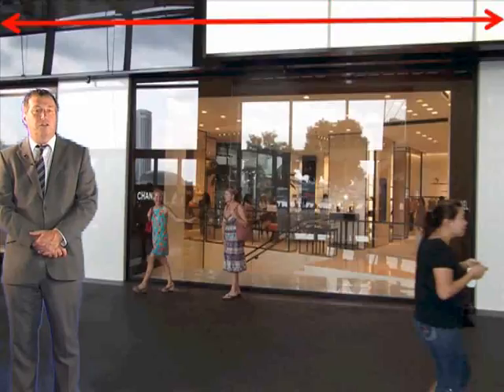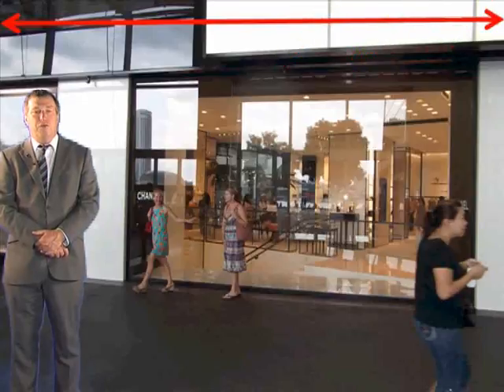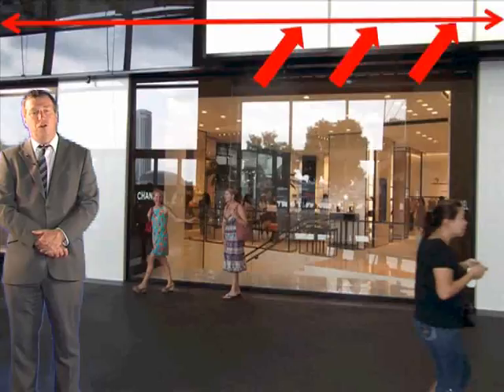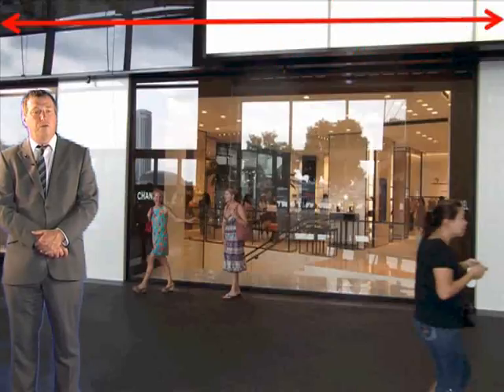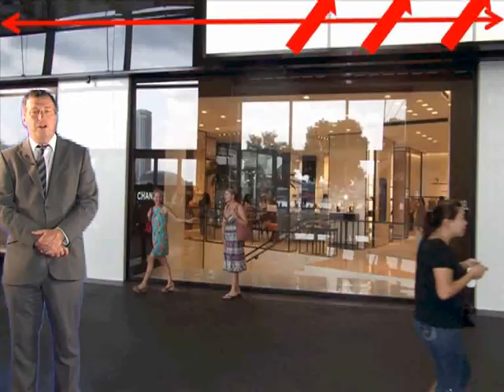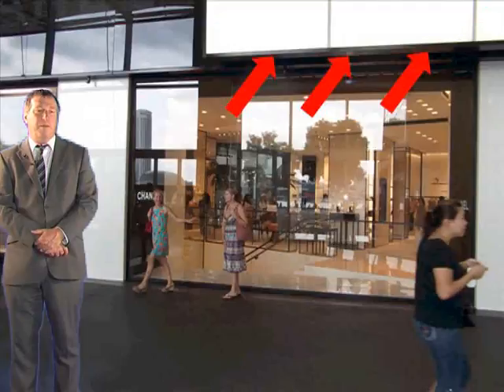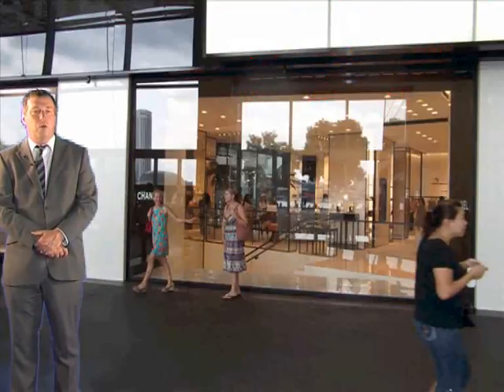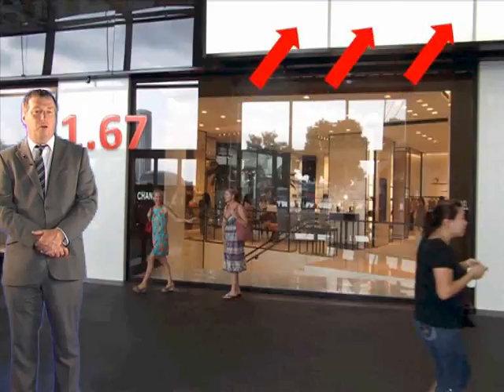As mentioned, the slot used for extraction must be at least as wide as the gap or opening through which smoke would otherwise pass. If, for example, it's being used at a shop front, then it must extend across the full shop front opening, including all the non-fire resisting glazing, as well as the doorway. The rate at which the slot extraction system must operate to ensure that no smoke can get past it is 1.67 times the volumetric extraction rate that would be required simply to remove the smoke.